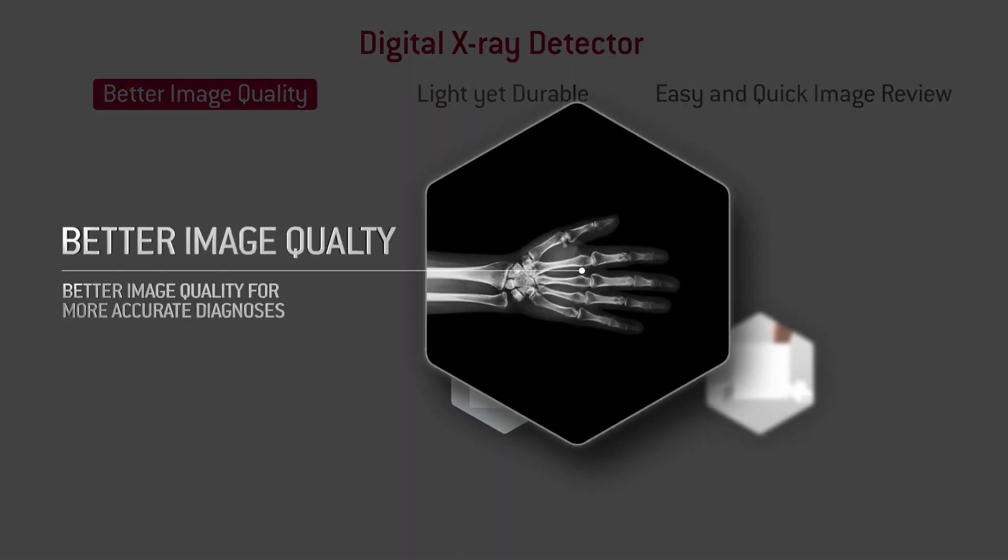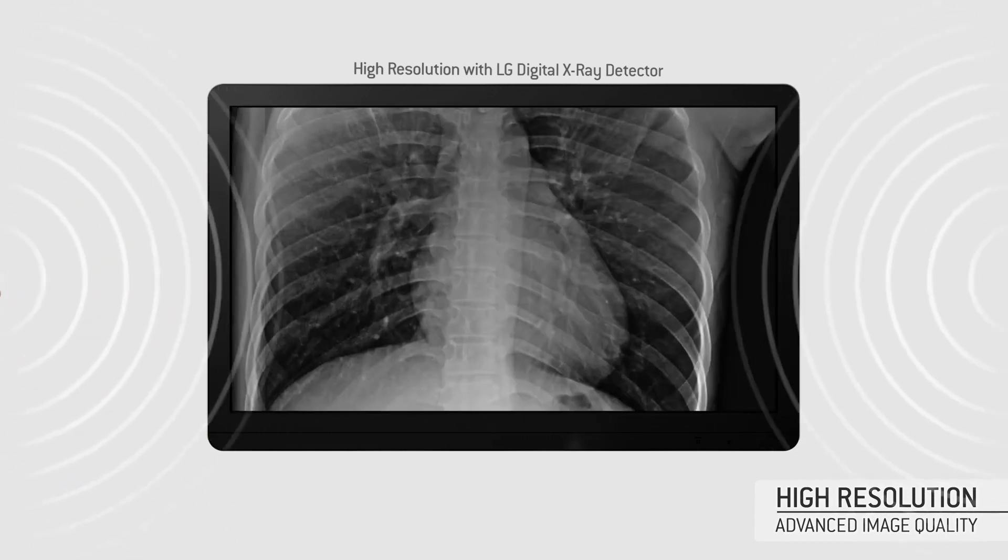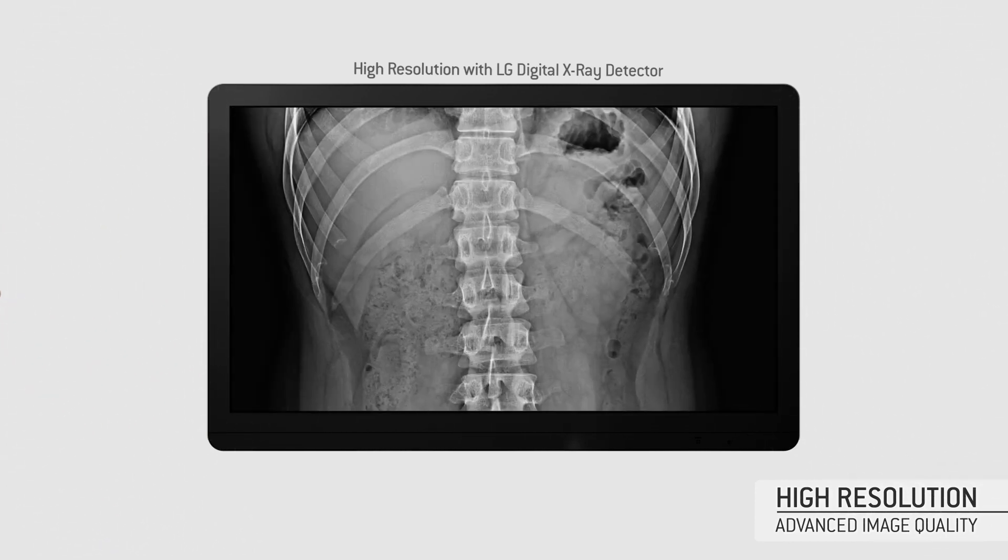Directly behind the scintillator layer is an amorphous silicon detector array manufactured using a process very similar to that used to make LCD televisions and computer monitors.